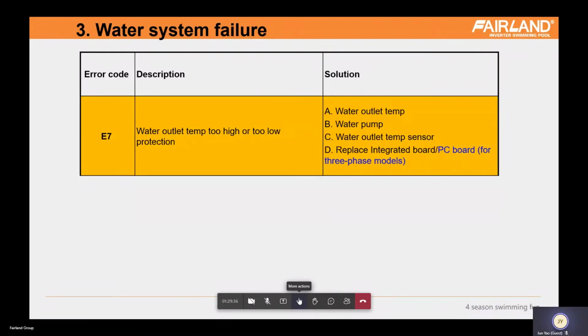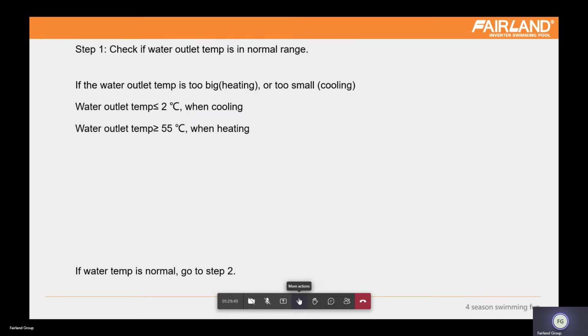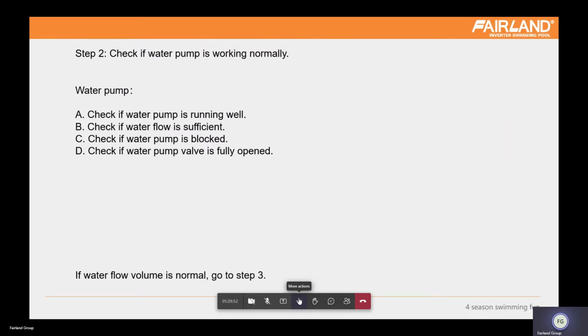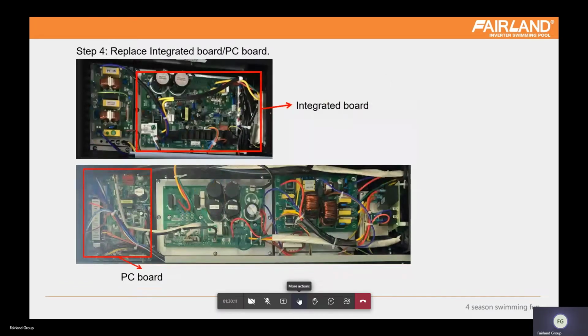And part three is the water system. Water system failure E7. I should say that E7 also almost never happens. The main reason is also the water flow volume. But when there is no water flow, it will cause E3. Little water flow will cause E6. So most of the time you will not see E7, but you can review it yourself.